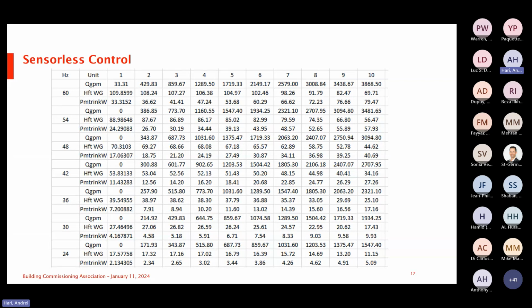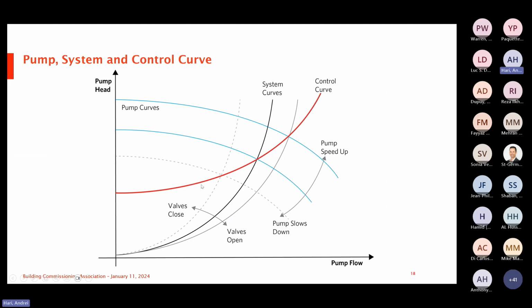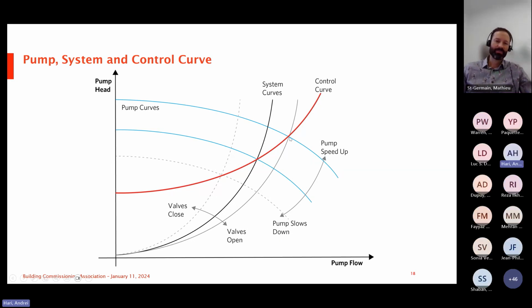All we're doing is overlaying the control curve. So now we define this. Basically, it's a quadratic equation, and this is where we're running. We determine the design point, which is the design of the building, and the minimum system pressure we typically specify at 40% of design. The control curve is calculated, and now all the controller knows is that it needs to run on this red line at any time. So if there's a change in the system, it just looks, sees we've deviated from this red line, checks what the data points are, and we get back onto that line.